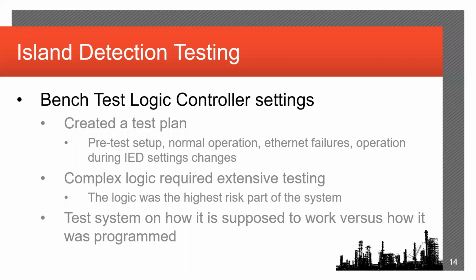And another one, I don't know if anyone's ever been burned on this one, but we specifically wanted to test the performance of a live system during IED settings changes. Like I said, we've been burned on that one in the past, and that was one of the specific tests that we wanted to make sure wasn't going to cause us issues. As I said, this is pretty complex logic, and it's just not one of those things that you could really test by inspection. It was really high risk, and it really necessitated a deep dive into the bench testing in order to vet that logic out.